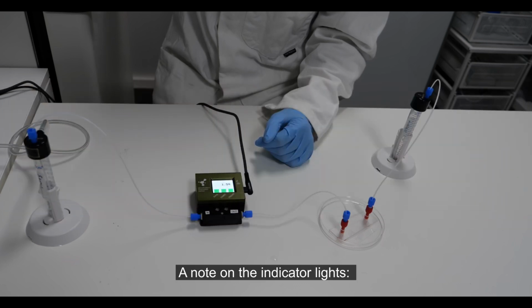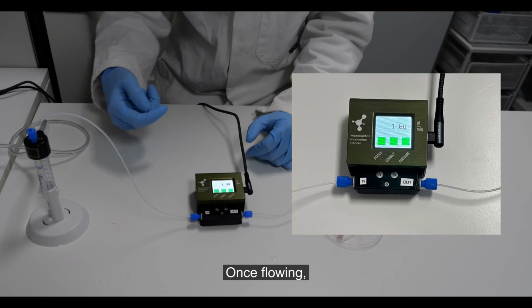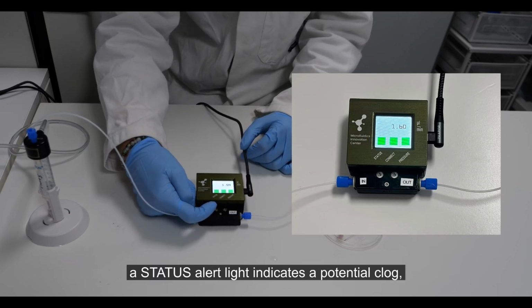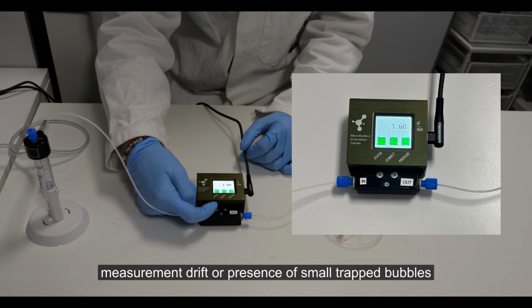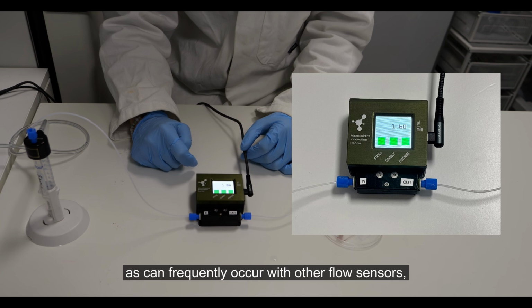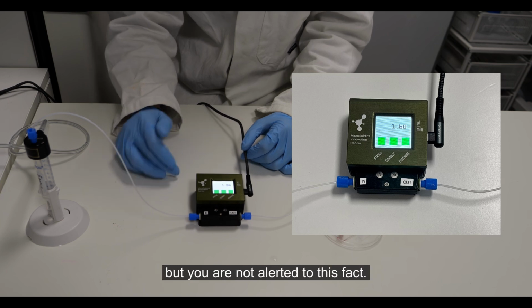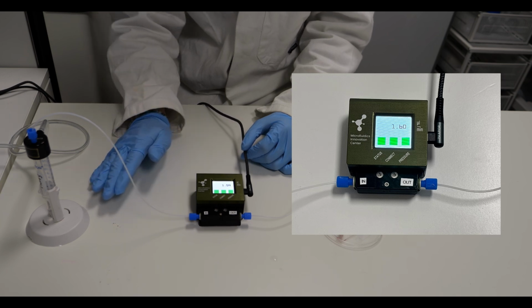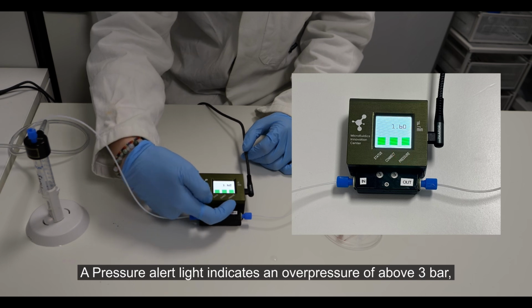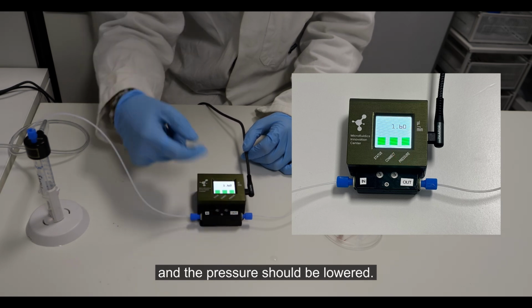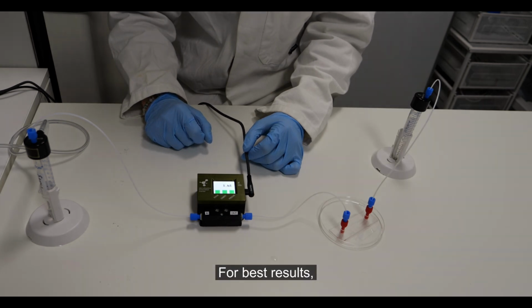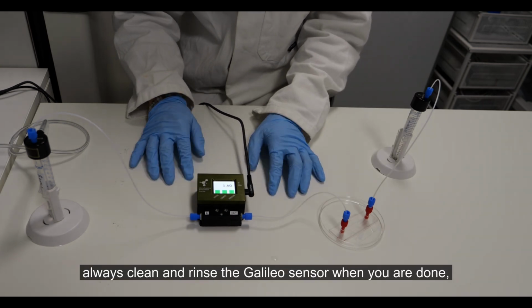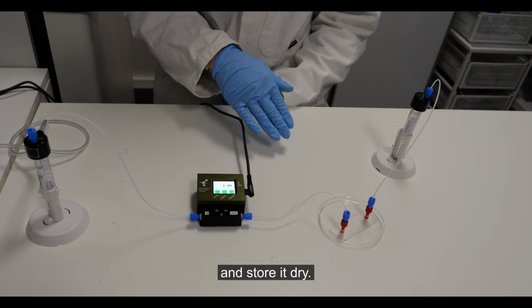A note on the indicator lights. Once flowing, a status alert light indicates a potential clog or measurement drift or presence of small trapped bubbles, as can frequently occur with other flow sensors, but you are not alerted to this fact. A pressure alert light indicates an overpressure of above 3 bar, and the pressure should be lowered. For best results, always clean and rinse the Galileo sensor when you're done, and store it dry.